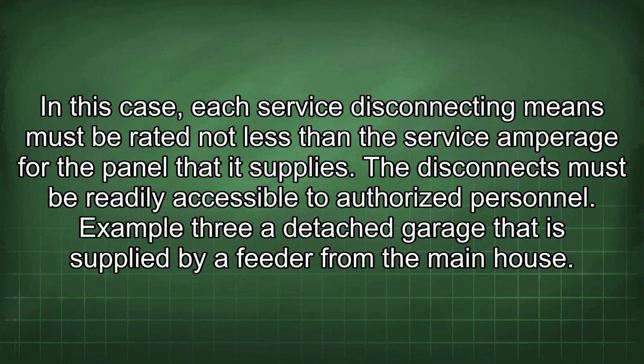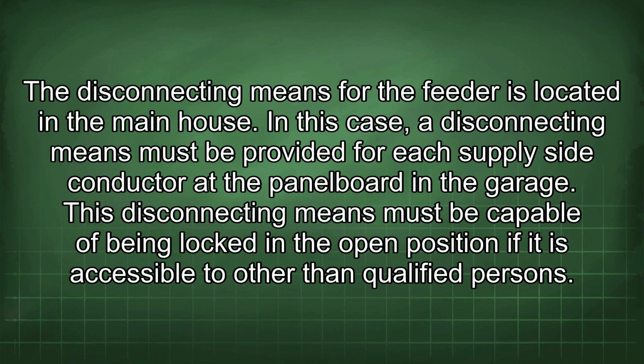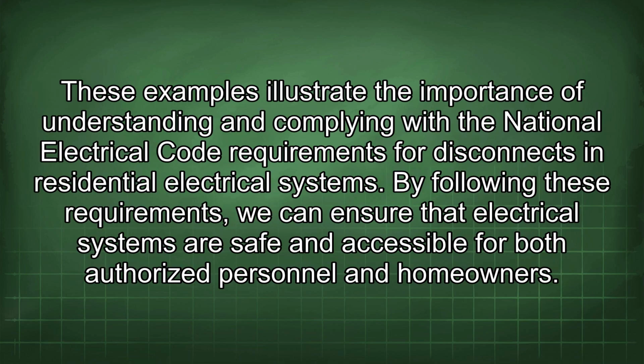Example 3: a detached garage that is supplied by a feeder from the main house. The disconnecting means for the feeder is located in the main house. In this case, a disconnecting means must be provided for each supply side conductor at the panel board in the garage. This disconnecting means must be capable of being locked in the open position if it is accessible to other than qualified persons.